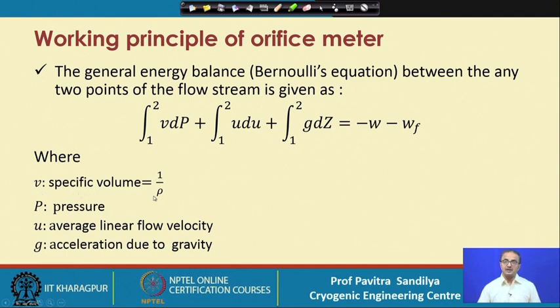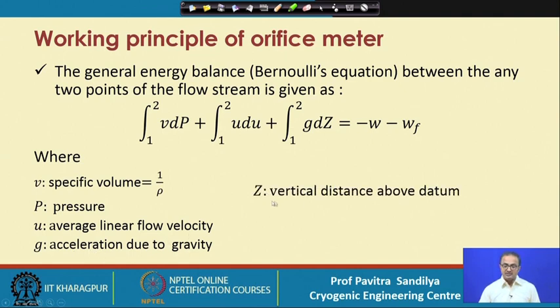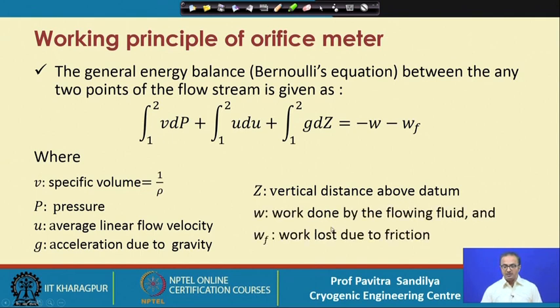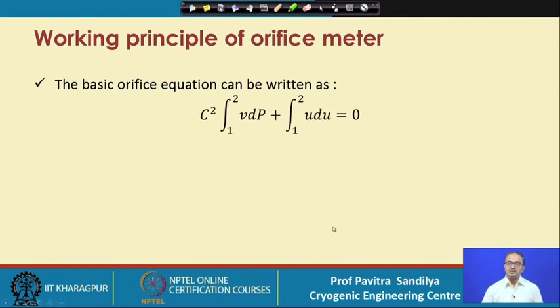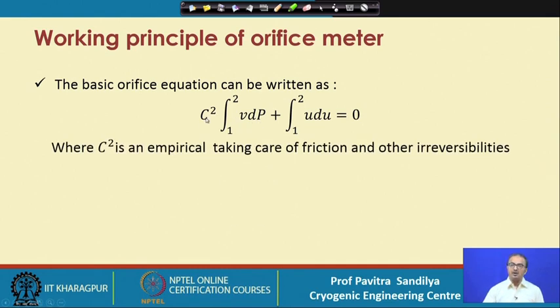Here V is the specific volume (the reciprocal of density), P is the pressure, U is the average linear flow velocity at a given cross section, g is the acceleration due to gravity, Z is the vertical distance from some datum, W is the work done by the flowing fluid, and WF is the work lost due to friction. After writing Bernoulli's equation we rearrange it, neglecting the potential energy — valid when the flow meter is horizontal — and introduce a parameter C which accounts for losses due to turbulence or any other loss.